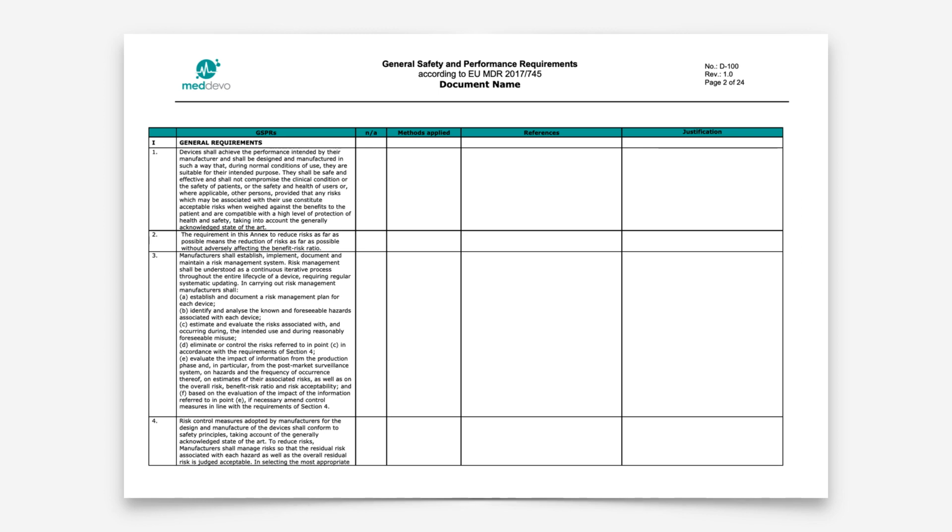If, for example, you want to show the notified body that you comply with a certain standard, then the version of the standard is also part of the verification document. You should also have documented how you have implemented the standard and what impact there has been. Finally, as proof of compliance, SOPs and verification documents, as well as a statement, should also be included in the document. Today we show what you have to pay attention to in order to set up and live the process.